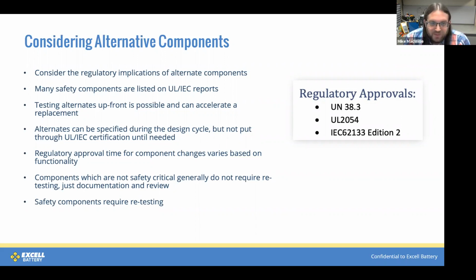The safety components are where you start to require retesting. So those are the FETs, the thermistors, the control ICs we talked about before. There's a little wiggle room if they're considered to be within the same family, but generally you're going to require some retesting. The evaluation of these is usually limited to the functional category, so if it's an electronic part, you're going to have to redo the electronic testing and maybe some of the temperature testing, that type of thing.